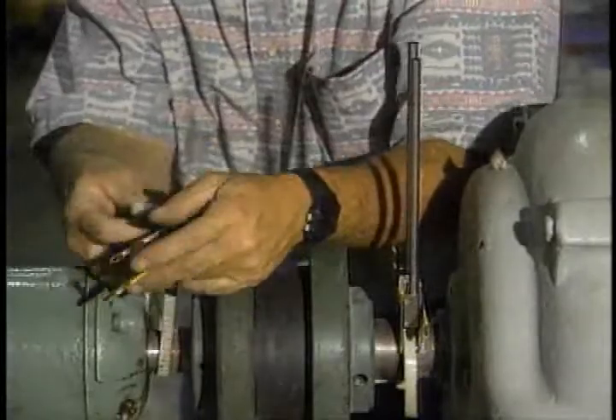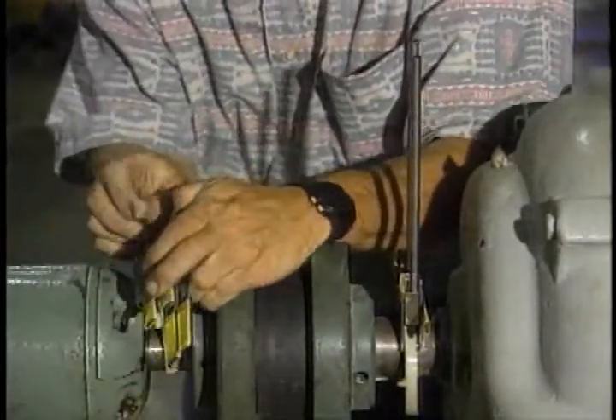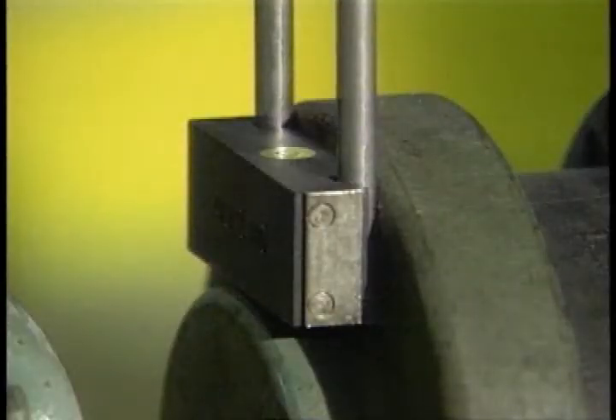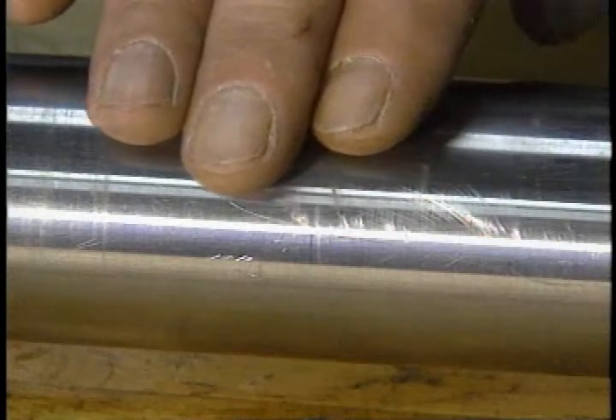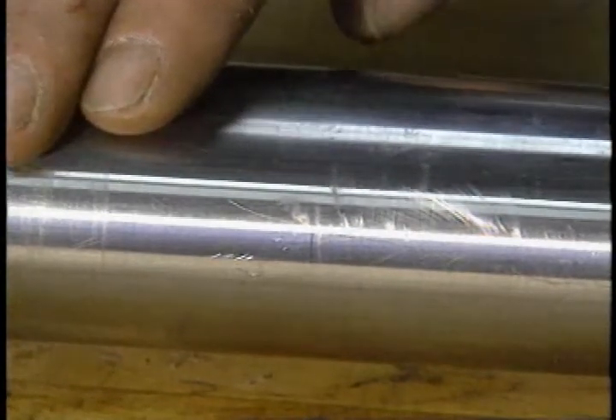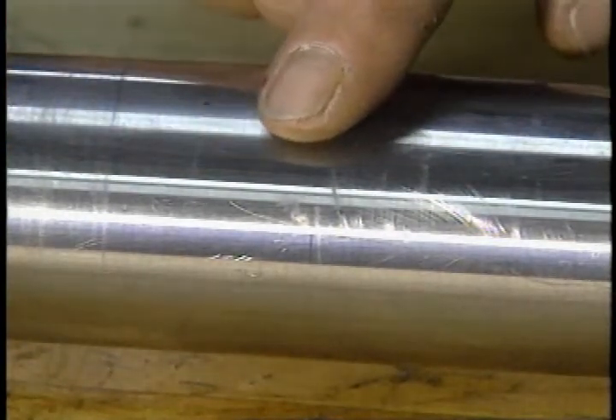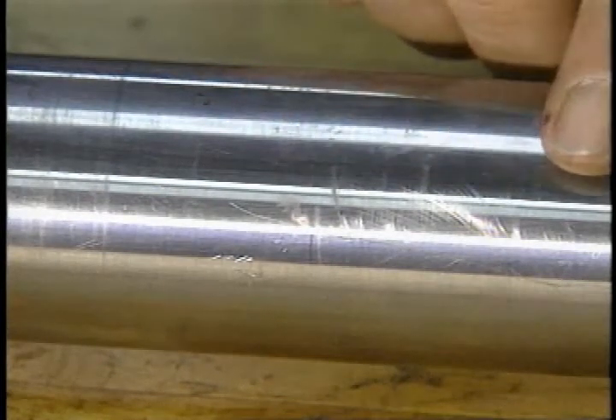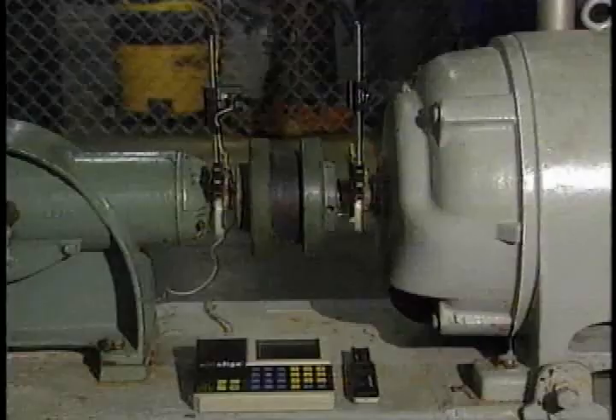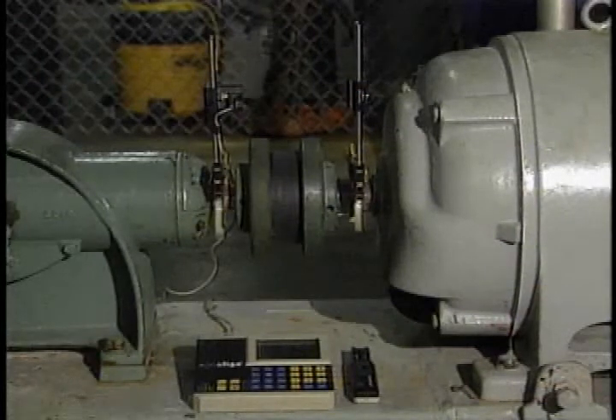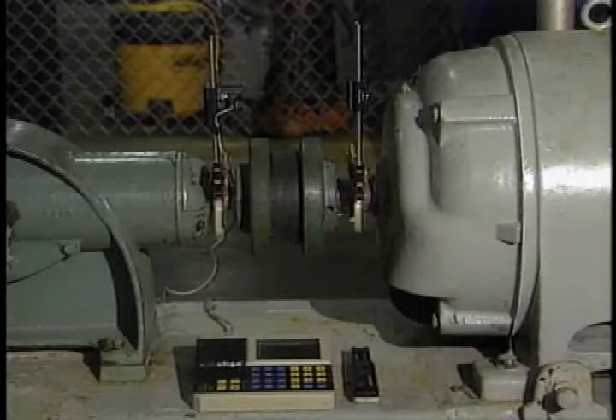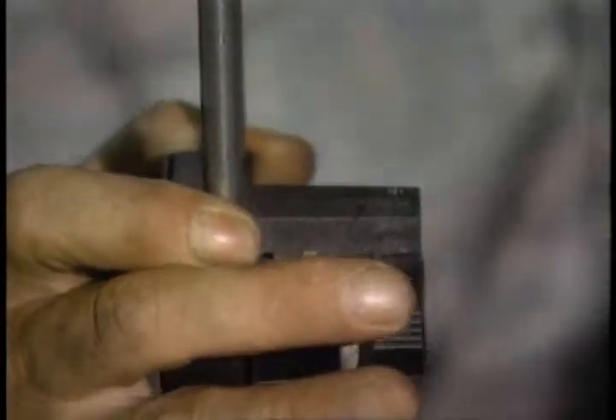Belt or chain brackets are most common. However, sliding magnetic brackets may be used when one or both of the shafts cannot be rotated. When using sliding magnetic brackets, the accuracy of the alignment will be dependent upon the surface finish of the shaft or coupling to which the magnet is attached. There are a variety of other brackets available to accommodate large couplings, tight situations, and other problem applications. Now, let's look at the optic heads.